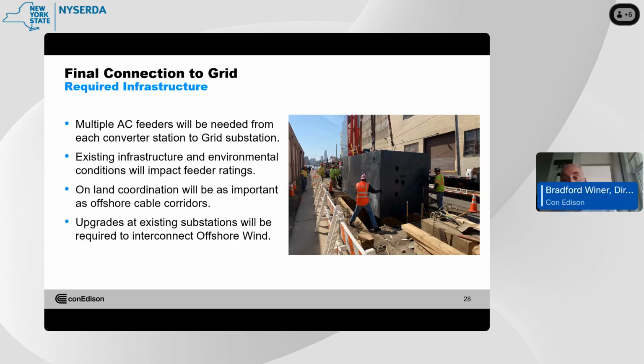If I'm running multiple circuits because I can't get the transfer capabilities due to environmental impacts or space restrictions, I'll ultimately need that much space for each additional feeder. So if we do some simple math, to get 9,000 megawatts of offshore wind we may need to run 14 feeders, 14 345kV feeders. We'll need to space manholes every 1,400 to 2,000 feet, depending on geographical constraints.